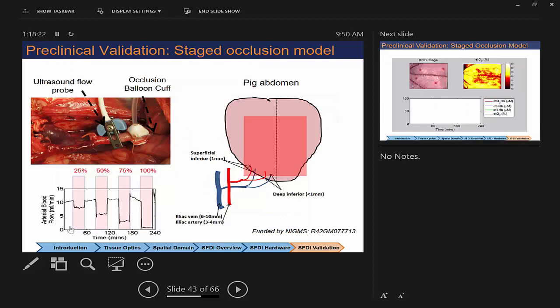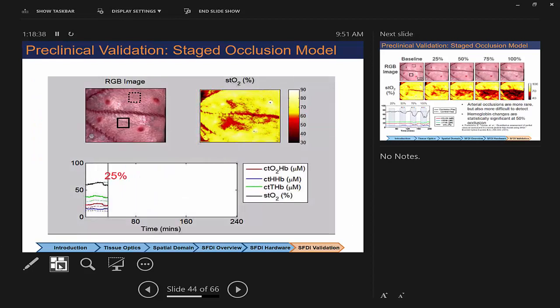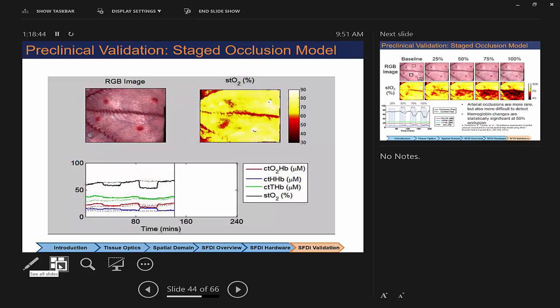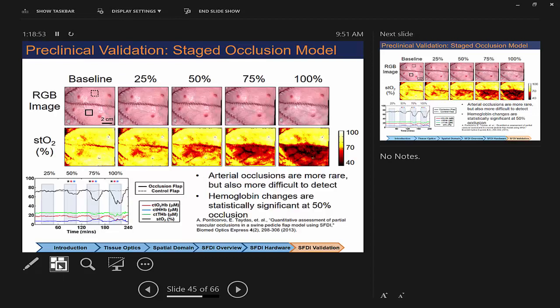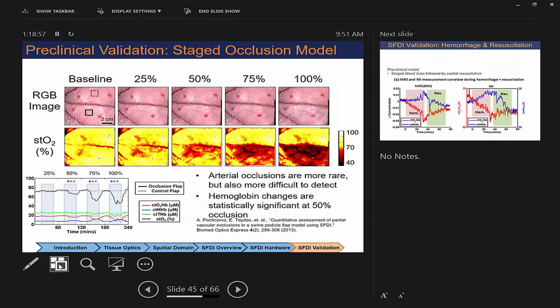Another is to, again, block blood flow into or out of a flap. This is the very first data image I showed. This is invasively. You can see there's a Doppler flow probe here and a balloon that allows us to block the blood flow or open it up. And this is what happens when you occlude and then release, and occlude more and release, and occlude even more and release. So this is over the course of 4 hours. And so we use this to validate the sensitivity of our device to these changes and to show differences between arterial and venous occlusion dynamics. We also used it to show that SFDI can see changes earlier than you can with your eye.